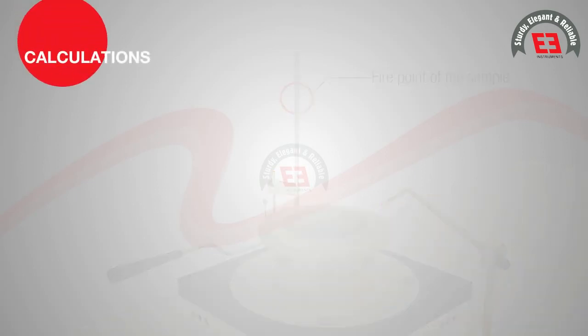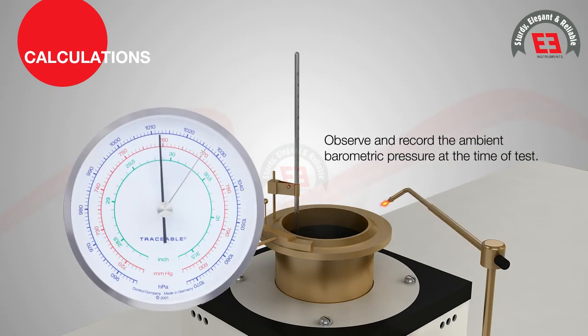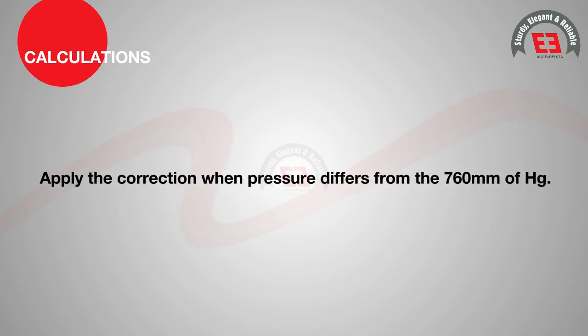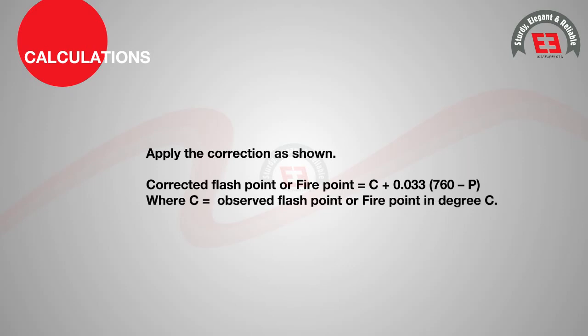Calculations. Observe and record the ambient barometric pressure at the time of test. Apply a correction when pressure differs from 760 mm of Hg. The corrected flash point or fire point is equal to C + 0.033 × (760 − P), where C is the observed flash point or fire point in degrees Celsius and P is the ambient barometric pressure in mm of Hg.